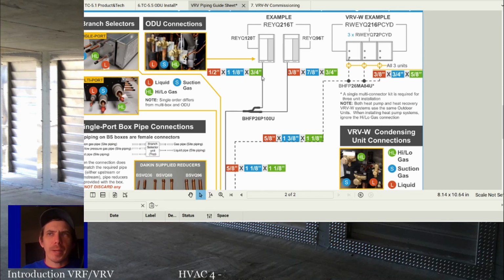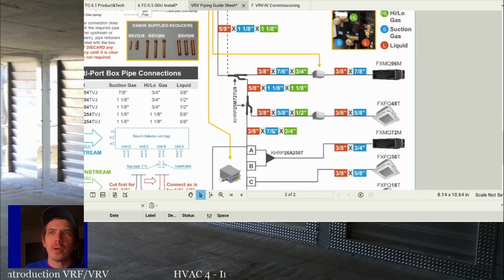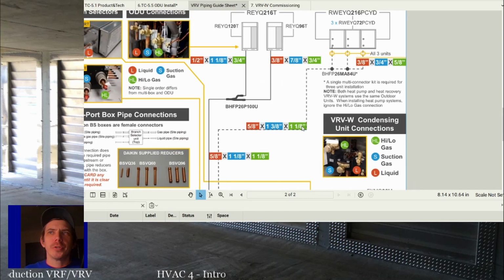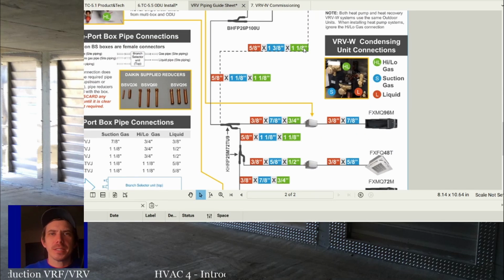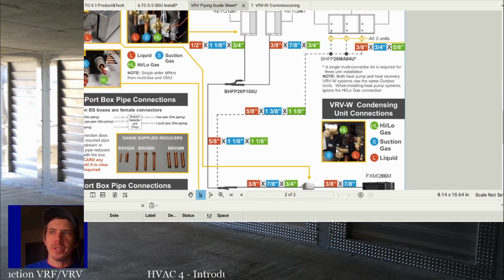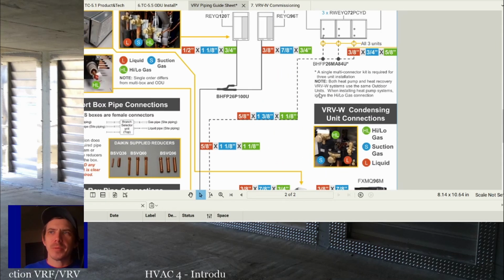Power is different for every manufacturer. Real quick on power, generally your outdoor units will get power, your branch selectors will get their own power, and your indoor units will get their own power. Some manufacturers, the indoor unit gets the power from the branch selector or vice versa. Some of them, they're all separate. But in general, you're going to have separate power feeds somehow, some way, to all the units. But this is very different from manufacturer to manufacturer, so I don't want to cover it too much.